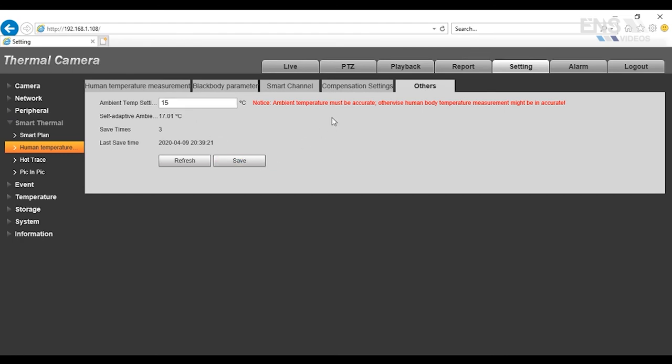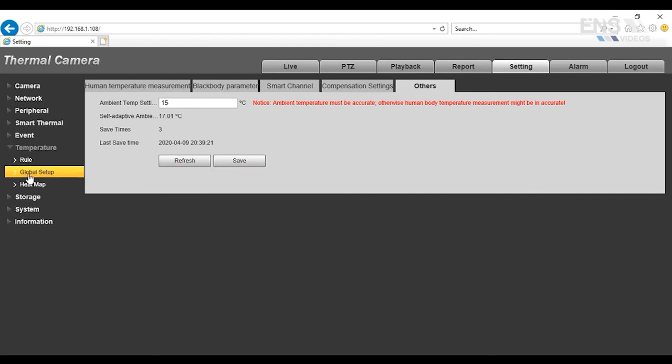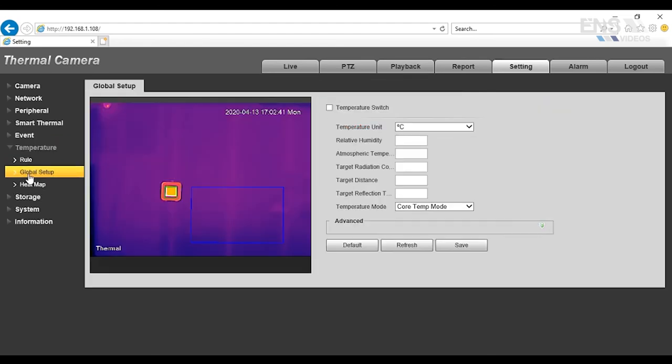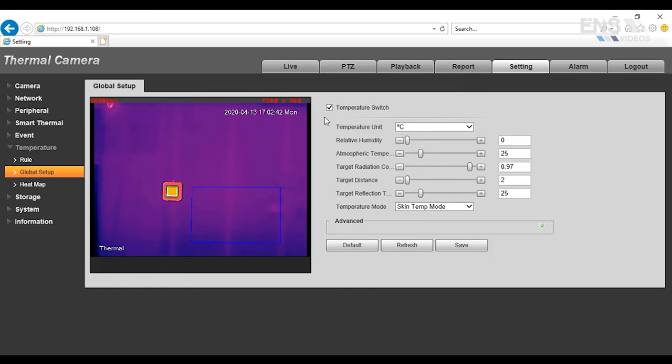Once that's done, you want to go to where it says temperature and go to global setup. Under global setup, you want to enable temperature switch. Now, after the firmware upgrade, you're going to have an option for Celsius or Fahrenheit, so it depends on what the customer's preference is. Once that's set up, then you want to select the skin temperature mode, and then hit save.